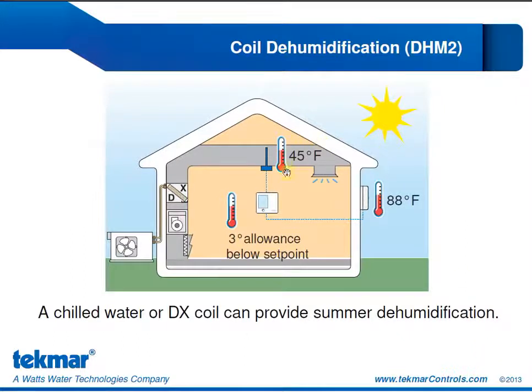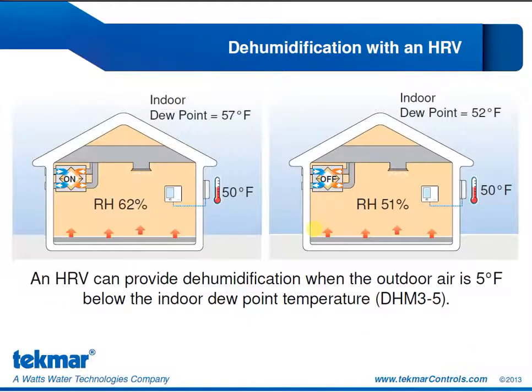To elaborate a little bit more on the coil dehumidification, you can see in this picture we're showing a temperature in the ductwork of 45 degrees, and this acts like a limit. If the air temperature in the duct falls below 40 degrees, we're actually going to turn off the compressors and not allow the dehumidification operation. So we're going to try and stay around 45. If it drops below 40, we turn off those compressors. We're also allowing the air temperature to fall up to 3 degrees below the set point. Because that air coming out from the dehumidification operation is going to be colder, it will fall a little bit. We'll allow it to fall up to 3 degrees before we turn off the compressors.